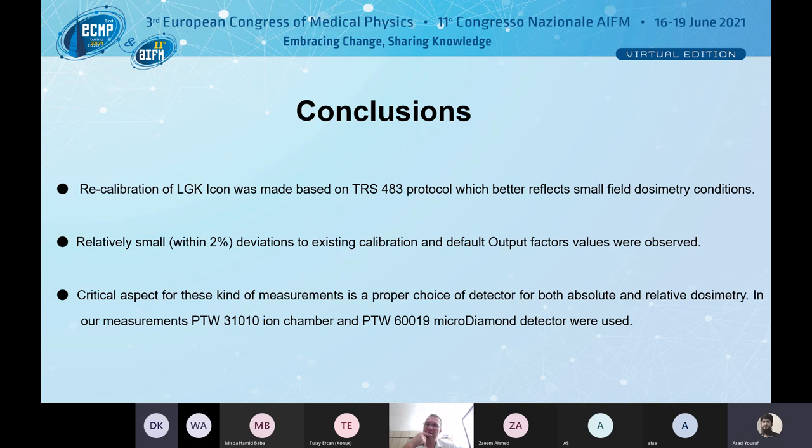About the Gamma Knife or CyberKnife, how do you calibrate? Basically, I just want to understand the procedure. Like our chamber is calibrated against the cobalt 60 NDW factor. So when you got your chamber, what's the procedure for the relative dosimetry? Yes, it's the same here in Czech Republic. Every 2 years, we have to go to the calibration laboratory.